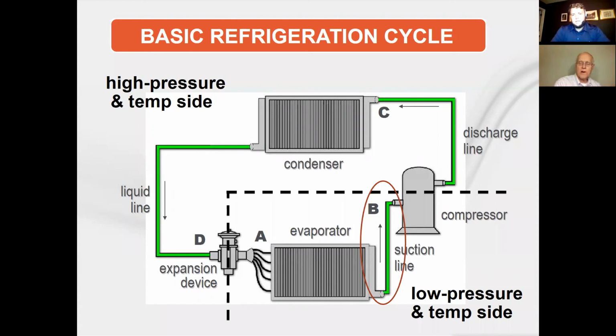You see it on computer room units again, where the compressor is typically in the indoor unit instead of out on the roof. So now they've got closer control on the piping from the discharge of the compressor to the reheat coil and back to the evaporator. They can control that a lot better. But when your compressor is far away from the system, if you think about the hot gas that you're sending to the reheat coil, it is probably going to condense a bit on its way to the reheat coil if it's far away. So it's not saying it can't be done. It's just not often done.